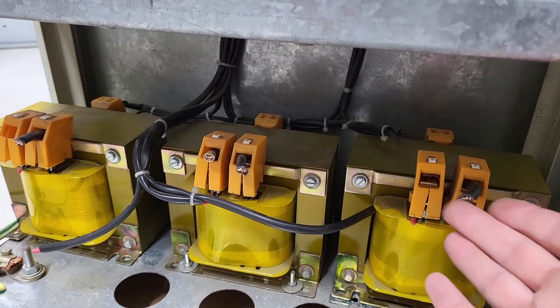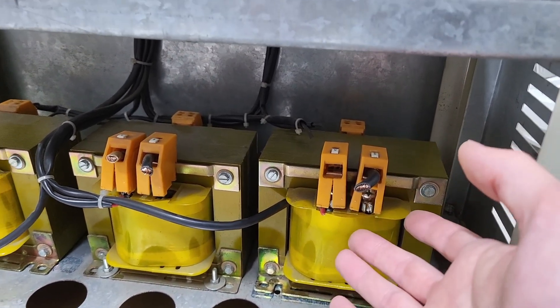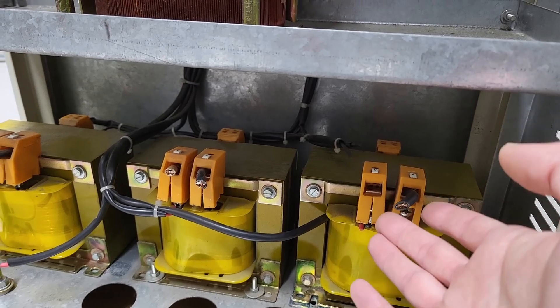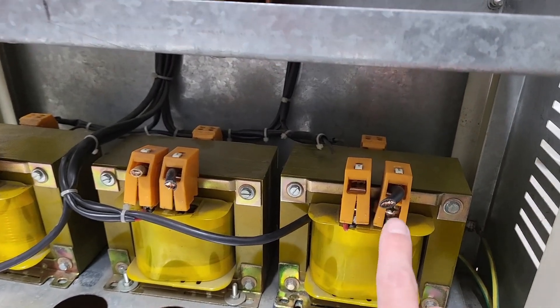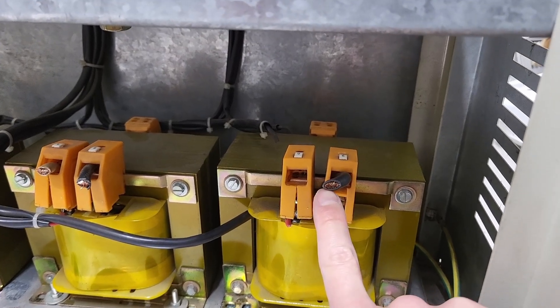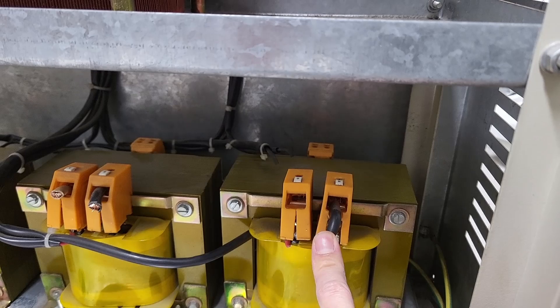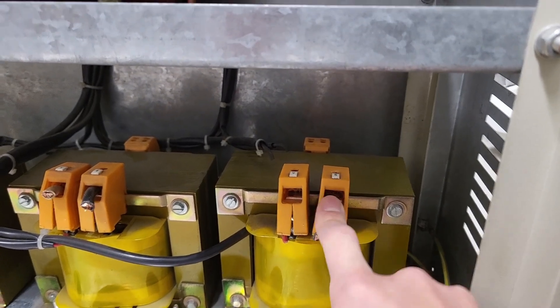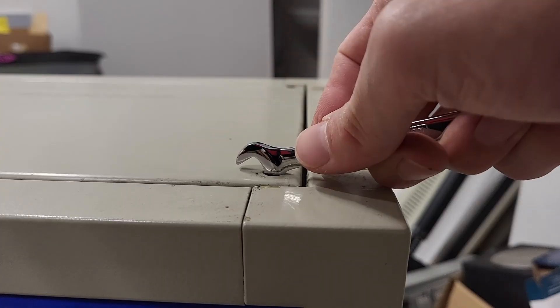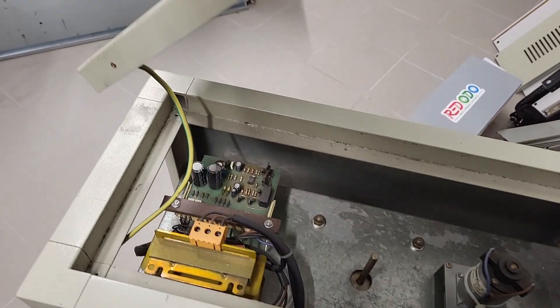The three transformers are relatively small, probably rated around one kilowatt each — no way they handle 22 kVA. One thing I notice right away is the secondary winding, which has much thicker wires and terminals. This may be the winding connected to the regulated line that actually carries the 33 amps. I'm going to remove the top cover to check inside.